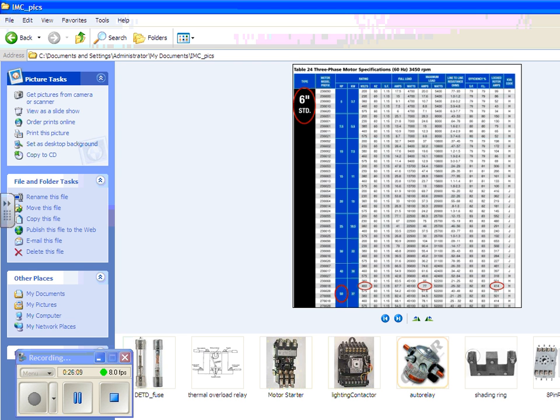There's a motor starter selection chart in our book. You're going to be getting an overload device selection chart sometime soon. And the front page will be this page right here on page 69. And it says NEMA size, and then it says the voltage of the load, then it says single phase or polyphase, and then it gives the horsepower. So they go down all the way to half horsepower single phase motors, and they go all the way up to 3-phase 575 volt 900 horsepower motors. That's a big motor.